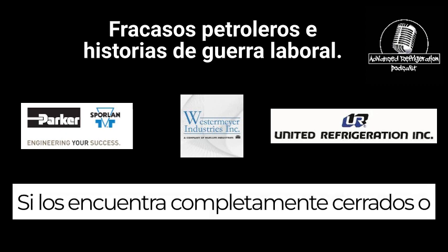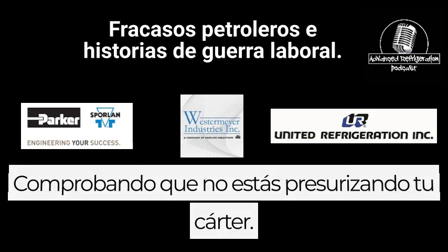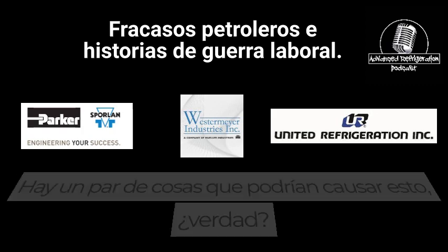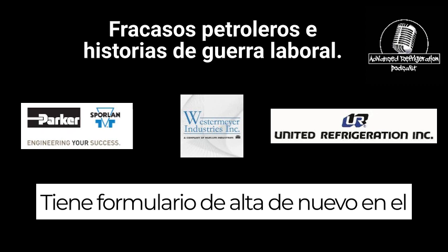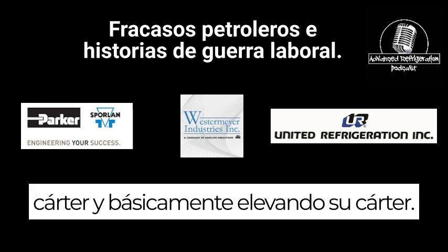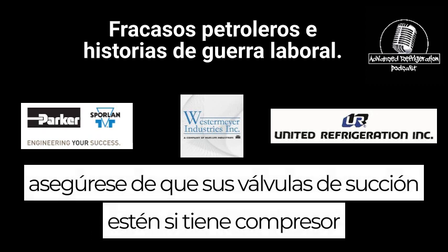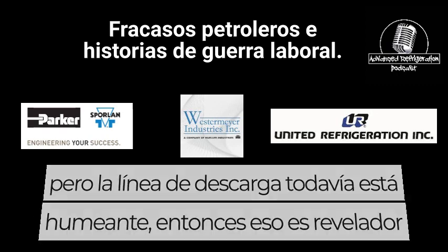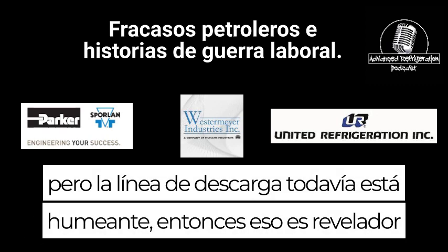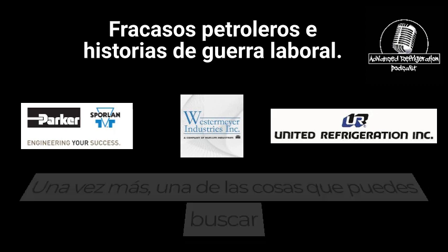If you find them all the way closed or open, generally. So three helpful hints is checking to make sure you're not pressurizing your crankcase. There's a couple things that could cause this, right? You could have suction valves, right? You could have discharge flowing back into the crankcase and basically elevating your crankcase. So if you do a pump down test, that'll check to make sure that your suction valves are in. If the compressor has been off for quite a while, but the discharge line is still smoking hot, then that's telling you that your discharge valves are bad, in fact shoving discharge back into your crankcase once again.